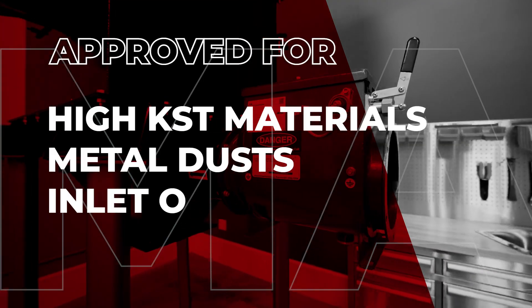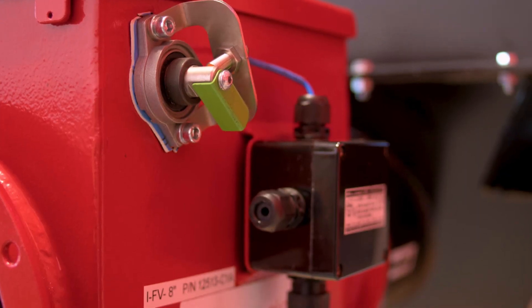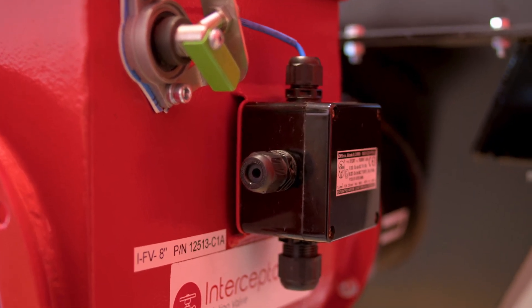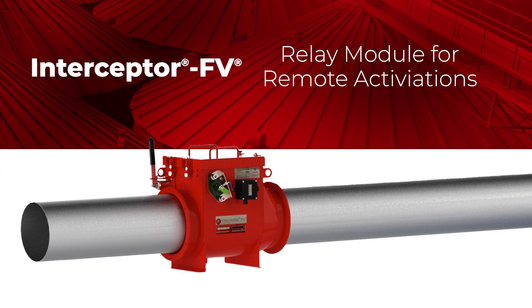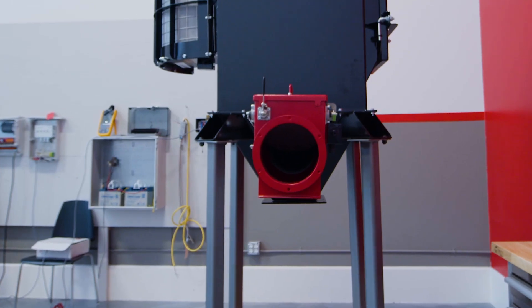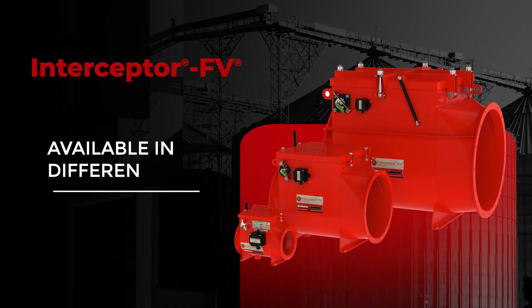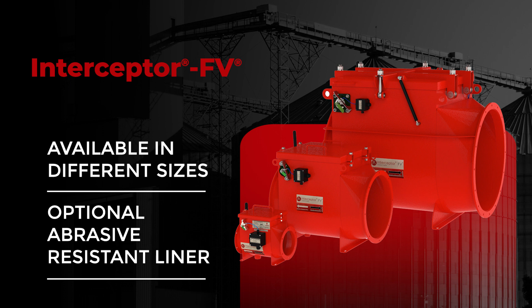The flap valve is also approved for high KST materials as well as metal dusts. The valve also features a dust accumulation sensor to detect material buildup inside the valve and a relay module to provide remote signaling for activations. The flap valve can be reactivated and rearmed in the field without vendor support. The flap valve is available in different sizes and can be optioned with an abrasive resistant liner.